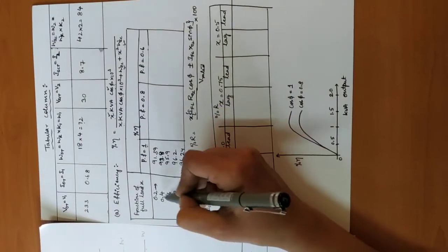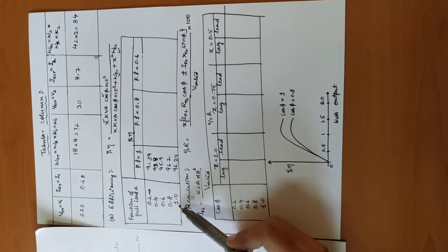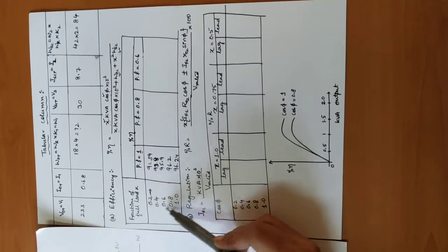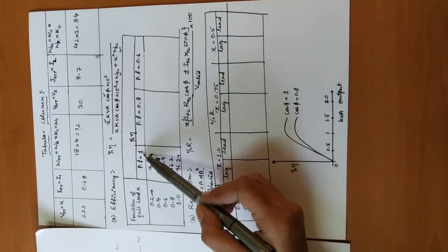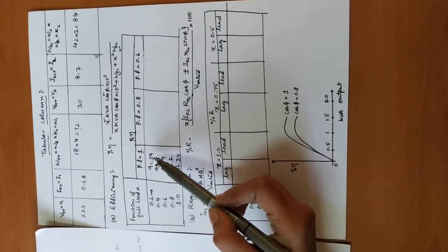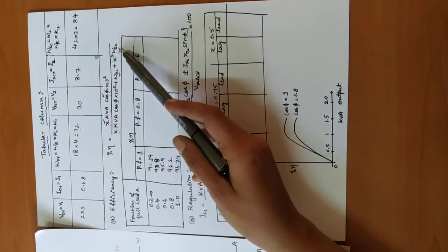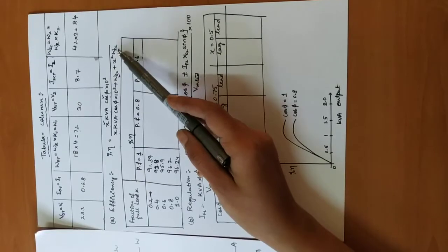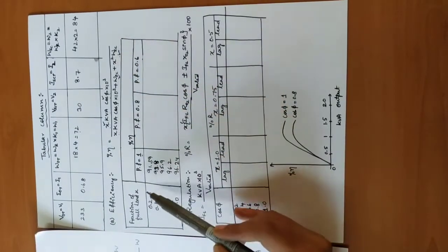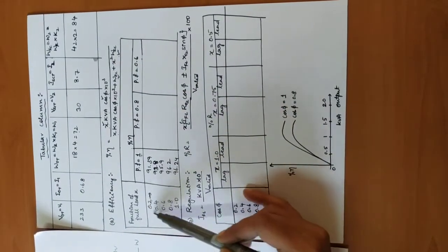It results in 91.389%. Similarly, the same calculation needs to be repeated for the 0.4, 0.6 fraction of load, 0.8 and also 1. The x value keeps changing. The power factor will be unity power factor, and the WOC and WSC will be as they are, the half of the value, but only WSC gets multiplied with x square. So you have to concentrate only on this fraction of load.